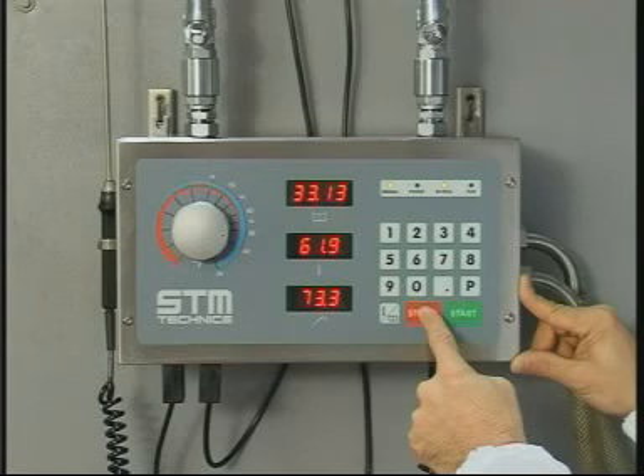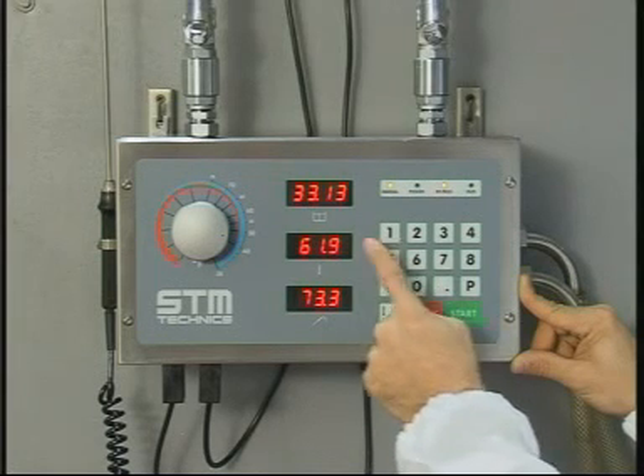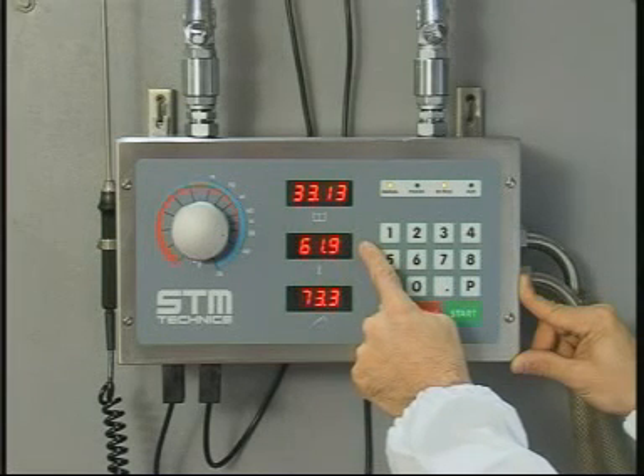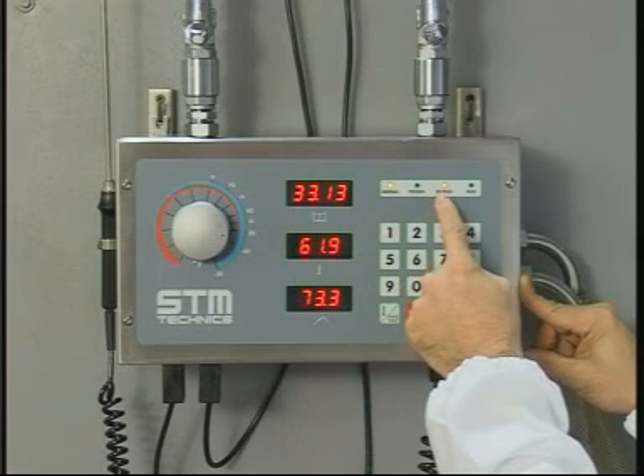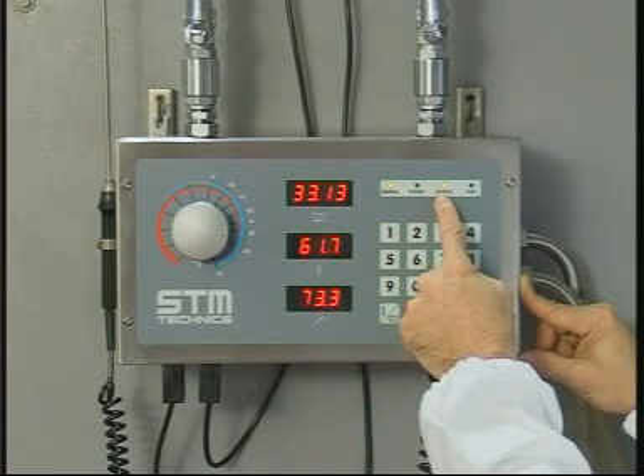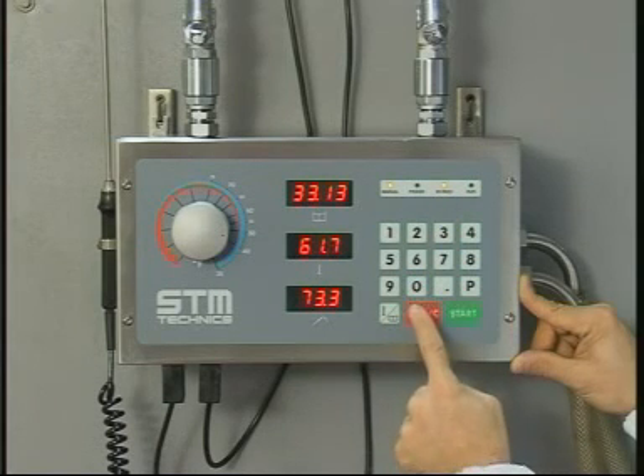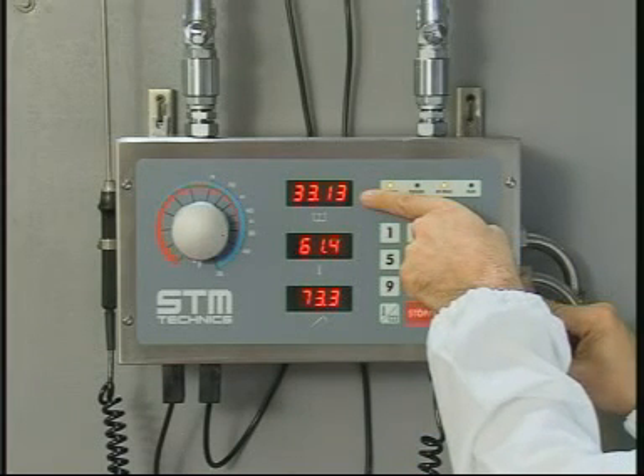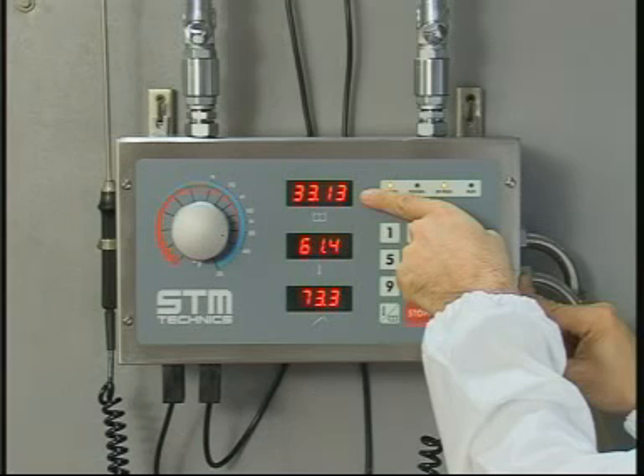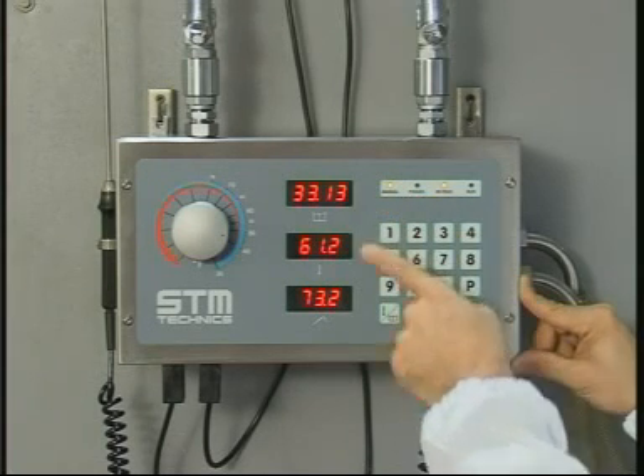If for some reason, with the bypass set in temperature mode, the temperature then goes out of the range programmed in the installer parameters, the delivery stops and the bypass indicator switches on until the temperature returns again within the allowed range. Eventually, adjust the temperature with the knob. At any moment, the delivery can be interrupted by pushing stop, and the remaining quantity appears on the upper display.